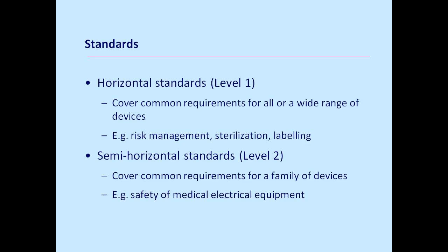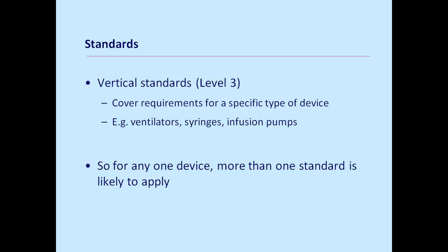The standards themselves can be grouped into different levels. So you have horizontal standards at level 1, covering common requirements for all or a wide range of devices. Examples of those types of standards might be risk management, sterilisation and labelling requirements. You've then got your level 2 standards, which cover common requirements for a family of devices, such as the safety of medical electrical equipment. And then you have the vertical standards, which cover requirements for a specific type of device, for example ventilators, syringes and infusion pumps. So for any one device, more than one standard is likely to apply.